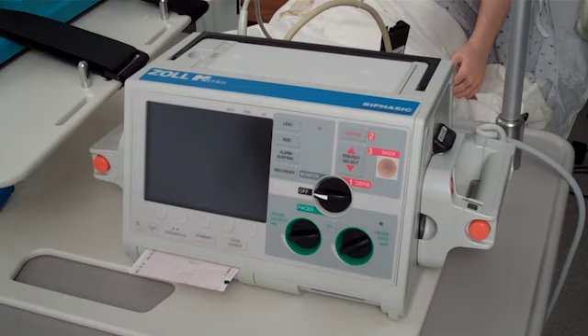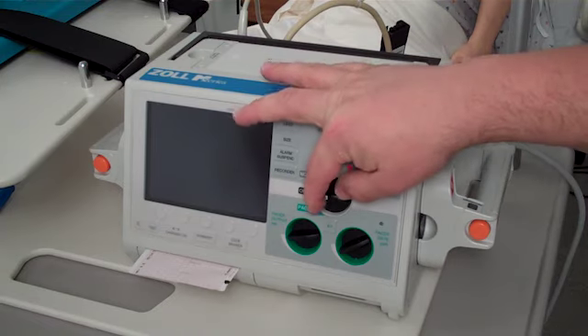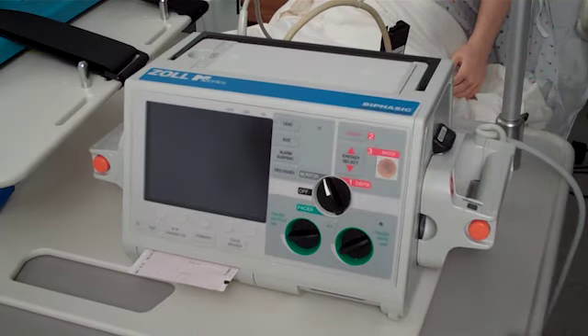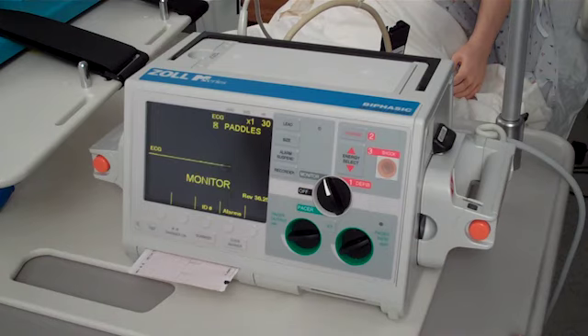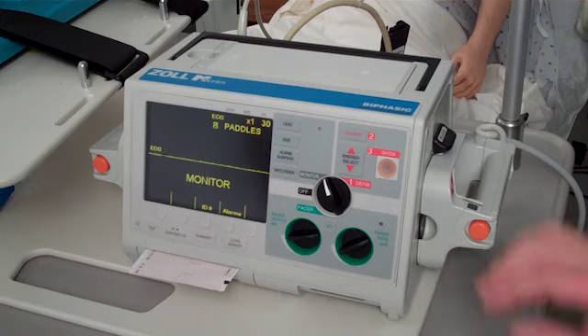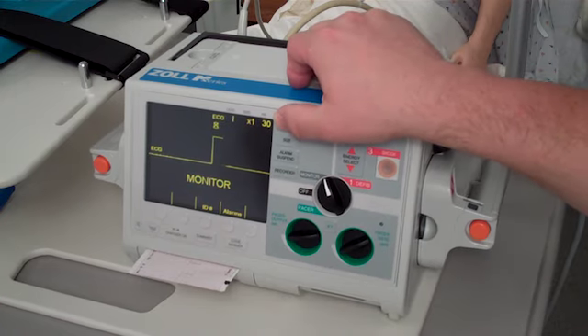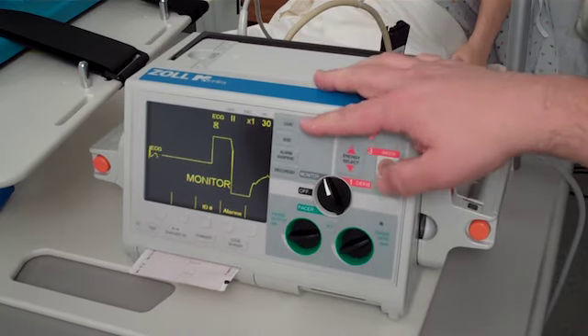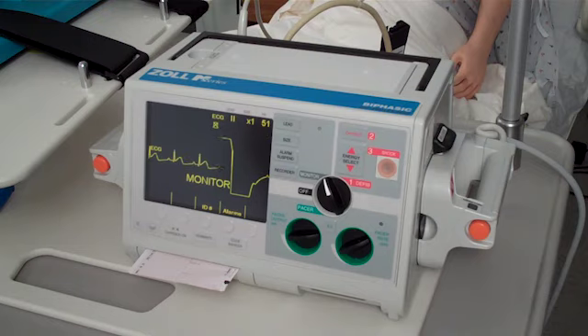After attaching the 3-lead monitor to the mannequin, as we'll describe in each individual mannequin section, we turn the master dial to monitor. When the machine comes up, it comes up with a default paddle view, so we need to change our lead to lead 2 by pressing the lead button 2 times. Once we do that, we can see the electrocardiogram.